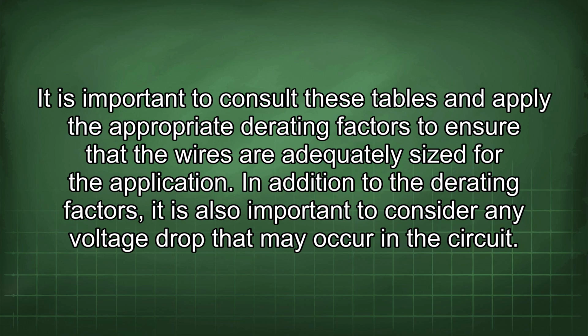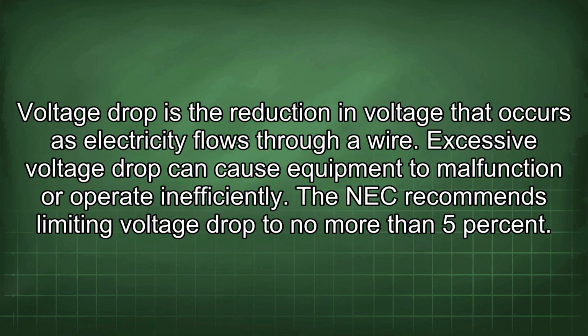sized for the application. In addition to the derating factors, it is also important to consider any voltage drop that may occur in the circuit. Voltage drop is the reduction in voltage that occurs as electricity flows through a wire. Excessive voltage drop can cause equipment to malfunction or operate inefficiently. The NEC recommends limiting voltage drop to no more than 5%.